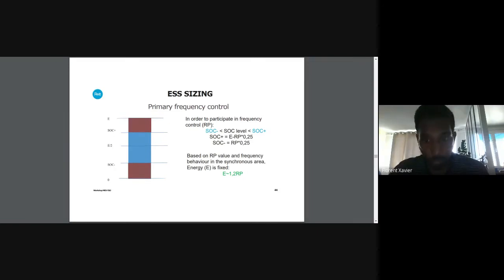And in continental Europe, we show that the energy of the battery has to be equivalent to 1.2 of the primary reserve that you would like to provide to the system. This scheme is very important in order to understand that you need to allow a certain range of power free to participate in frequency control. So a producer can use the battery between SOC minus and SOC plus, but never go further.